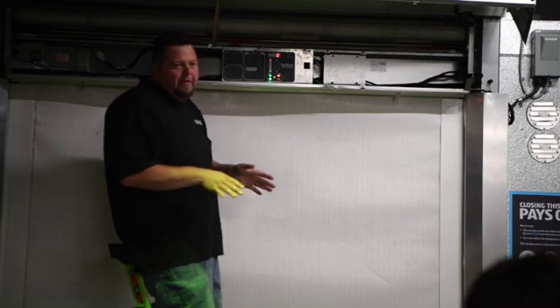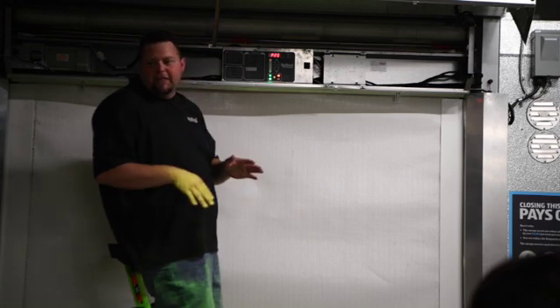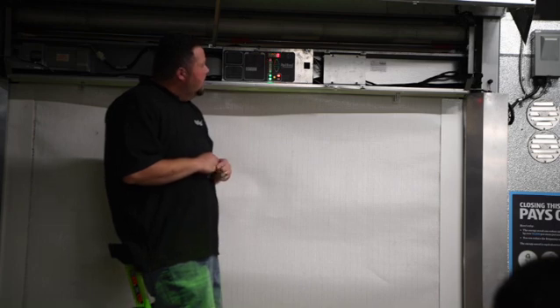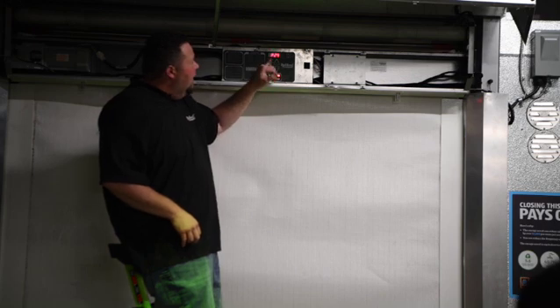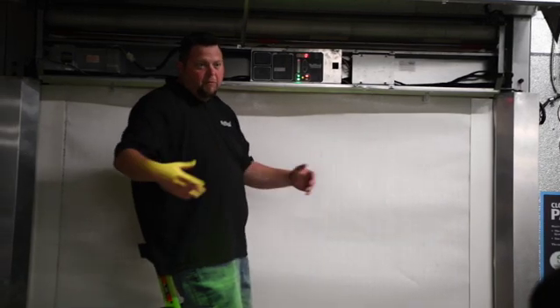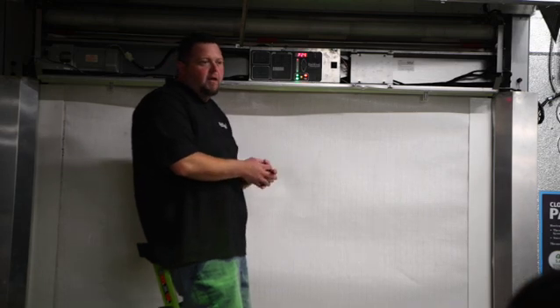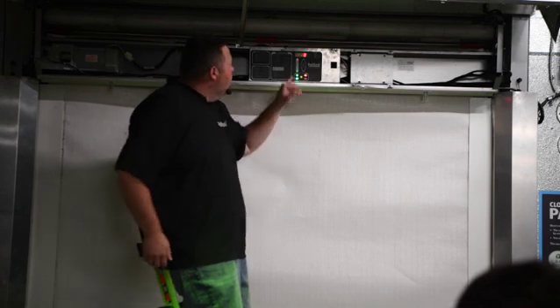P23, it's on 0. It will always be on 0. There's an option to change it. We're not changing it here in this setting. P24, that is that second dry contact. And you'll see on this one, I think we send it out on 0, but you can only change it to 1, which is fully closed. But if you have to read open for 2 different signals or whatever else it may be, just double up in your open, in your first auxiliary. You can put multiple things on it because all it is a dry contact, so it's not taking a lot.